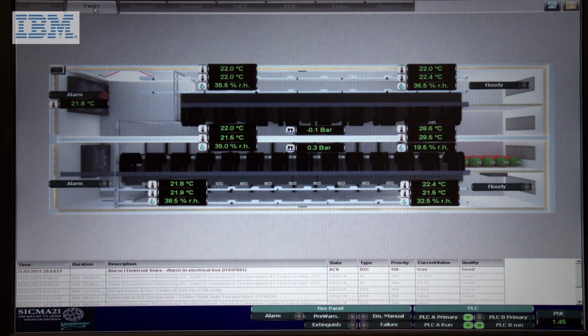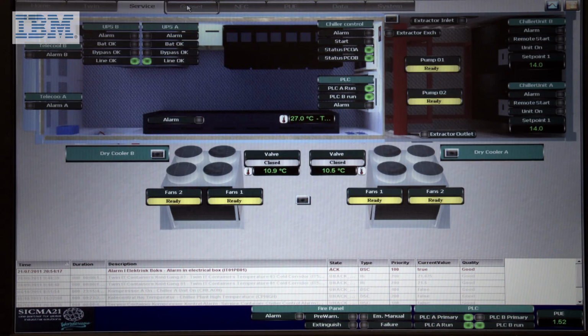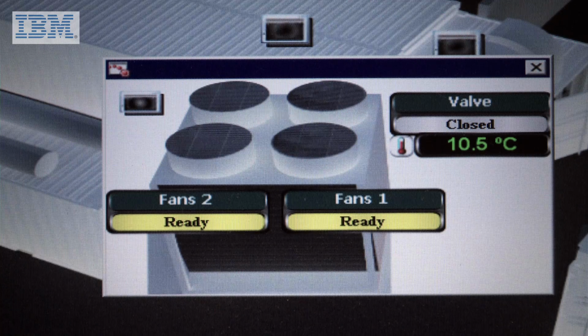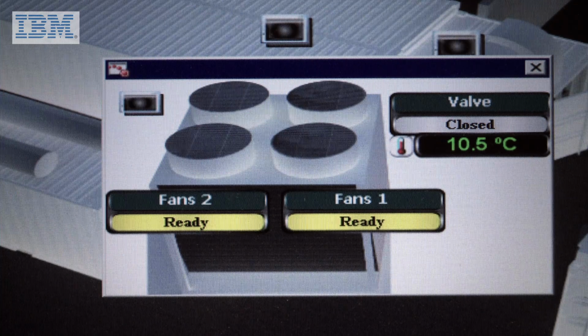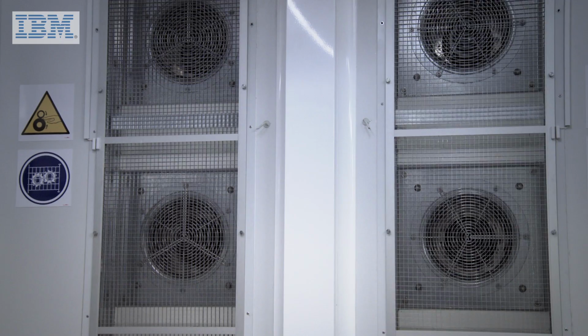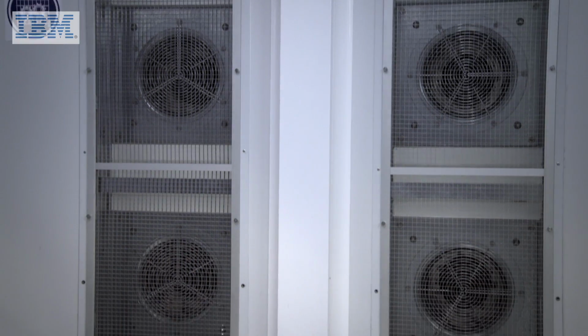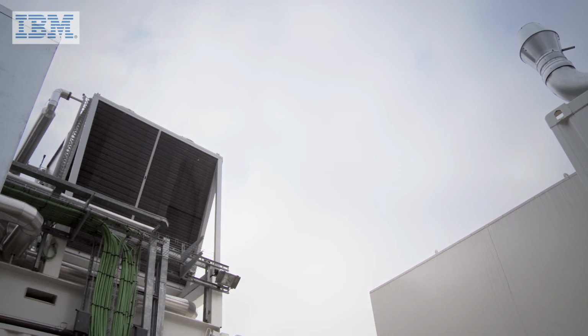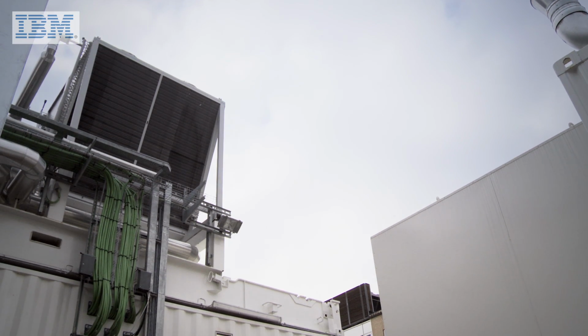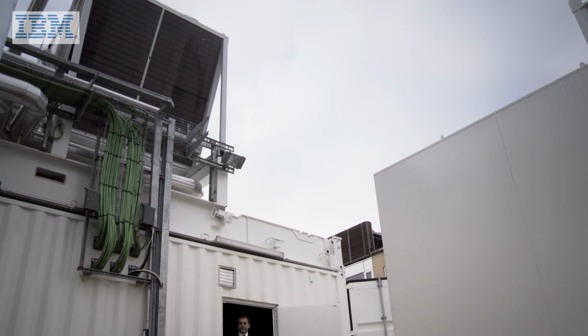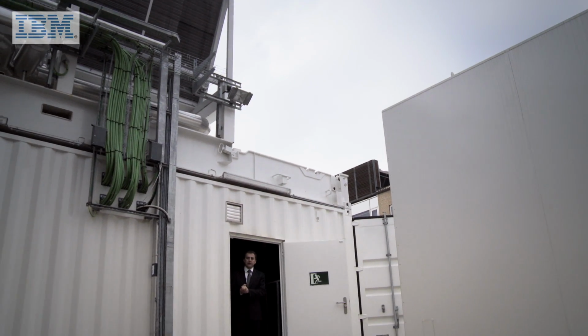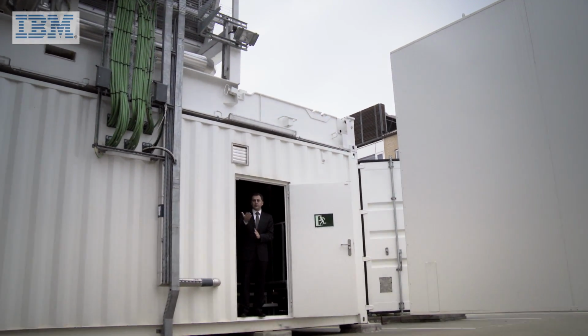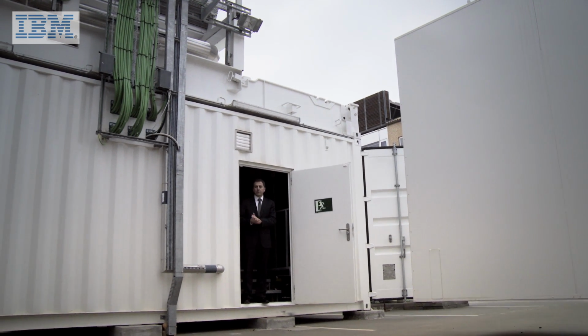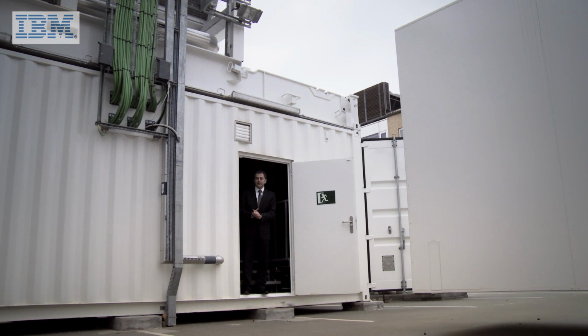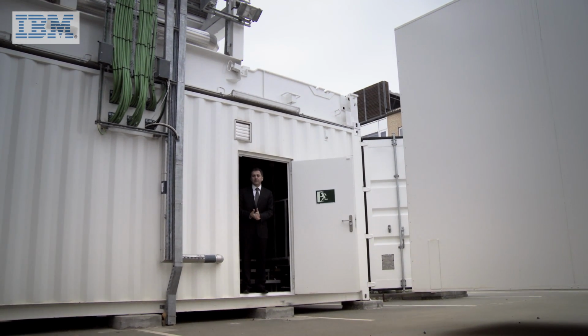The natural free cooling system is managed by the SCADA system, which controls different sensors: external temperature, external relative humidity, pressure in the IT cold corridor, and temperature in the hot corridor. Based on all these parameters, the SCADA system will send signals to the EC fans to accelerate speed and increase the airflow, or decrease it. This is the cooling backup module. This module contains chillers and dry coolers in order to provide chilled water to reinforce the natural free cooling system for those days where temperature may rise to levels where natural free cooling is not effective enough. This is probably about 4% of the yearly hours.